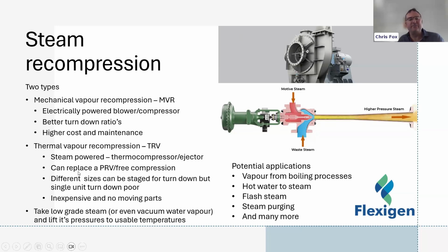Effectively, similar to the back pressure turbine, look for places where you've got a big pressure reducing station, and then look for another place where you have a source of low-grade steam or even hot water, which if you put a vacuum on, you could turn into medium pressure steam for a heating process. And in a situation like that, the compression's pretty much for free.